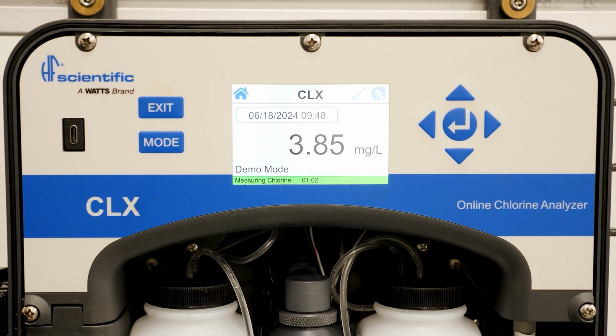Yellow indicates a warning and red indicates a halting error. An example of a yellow warning is a milliamp loop open. Yellow warnings mean the analyzer can run, but is alerting the user to an abnormal condition. The red banner indicates a halting error, such as an LED failure or solenoid error. This means the analyzer will not run and needs immediate attention.